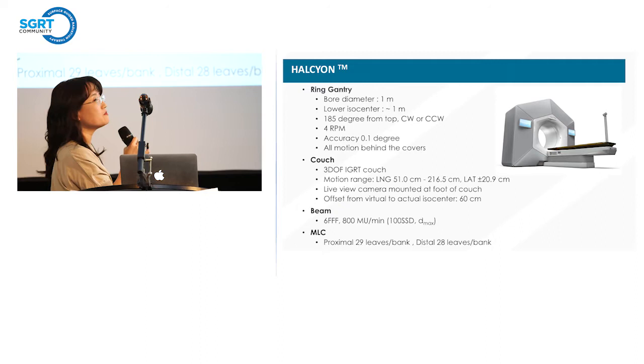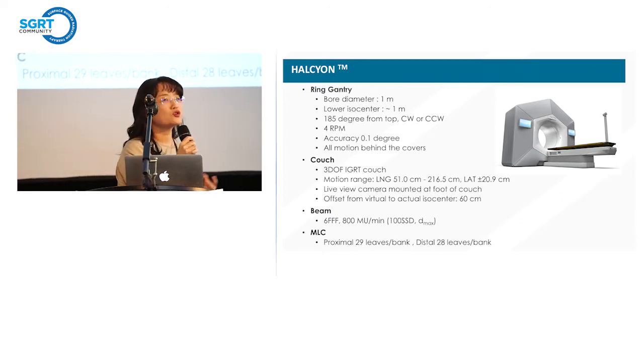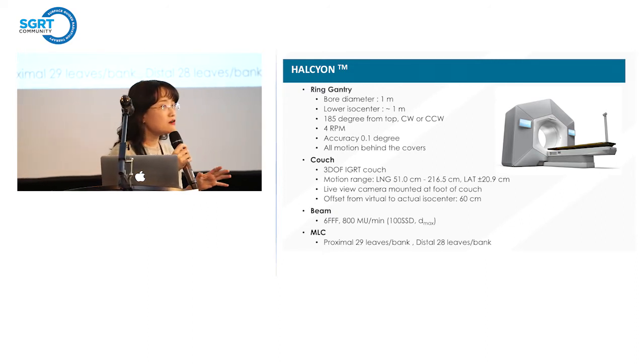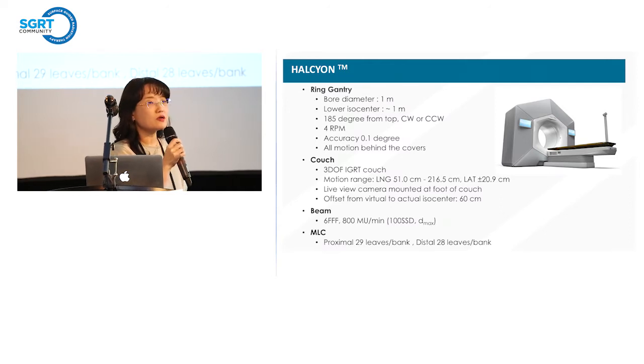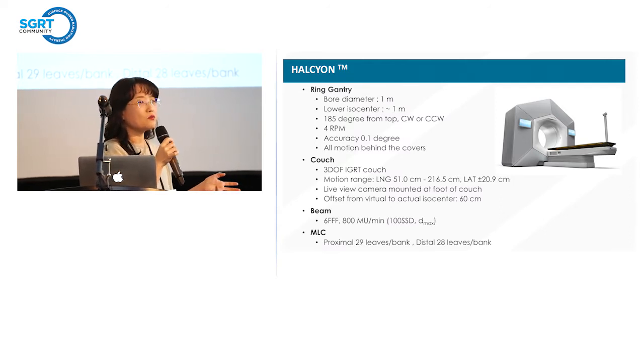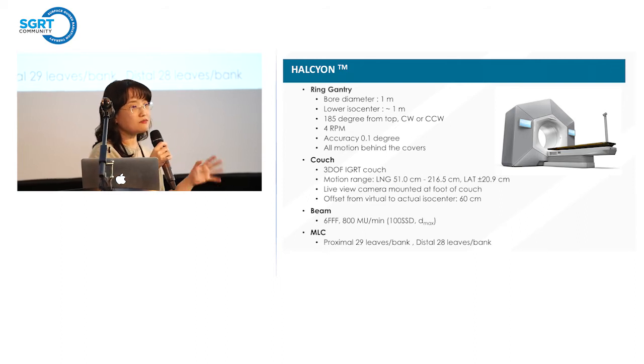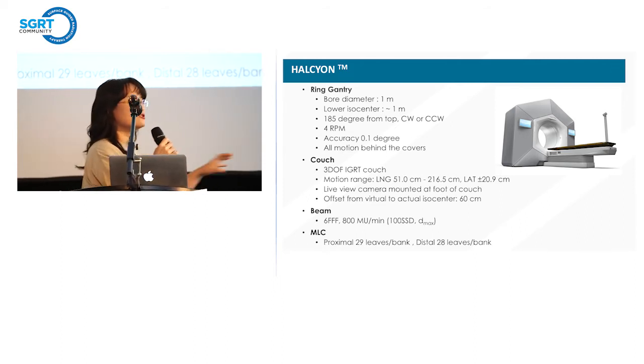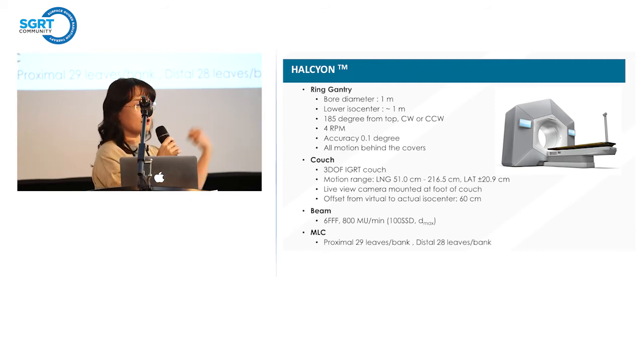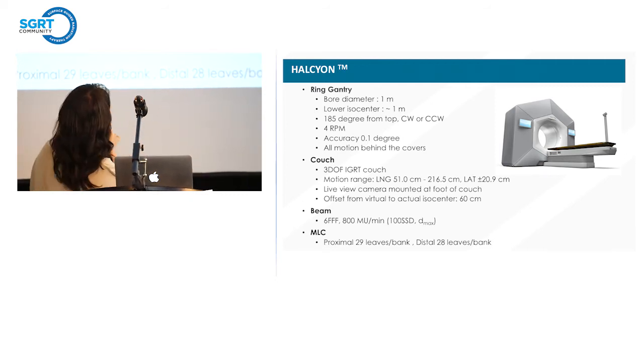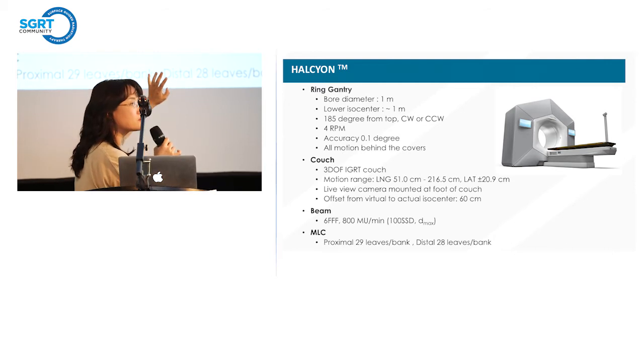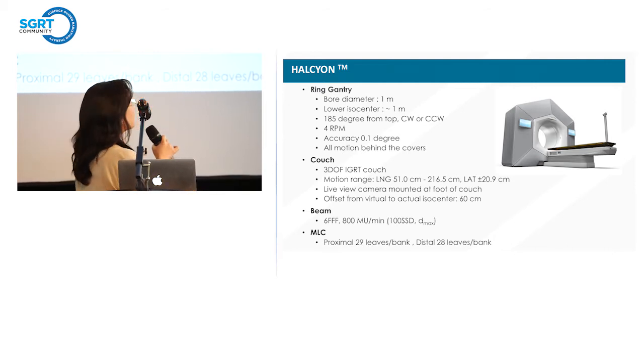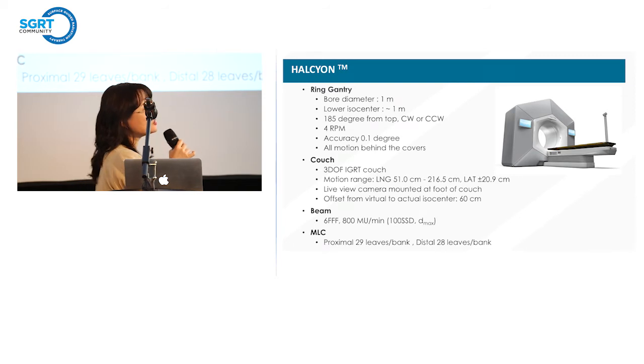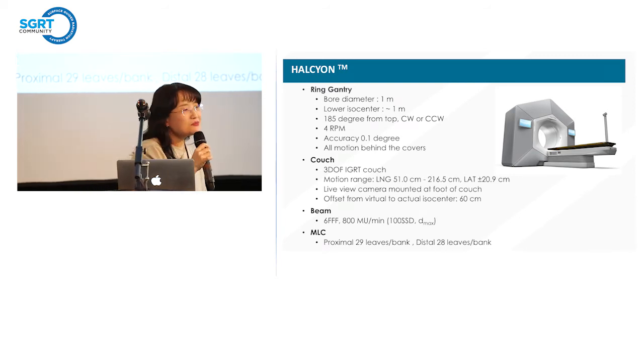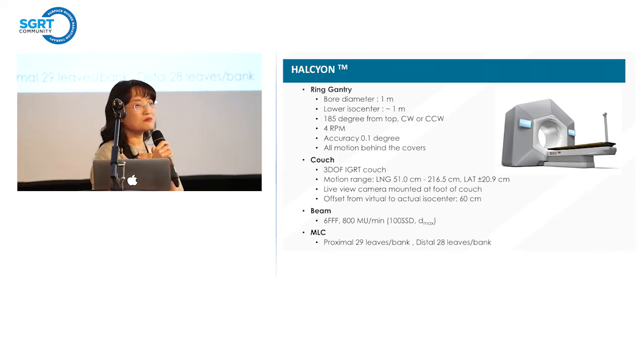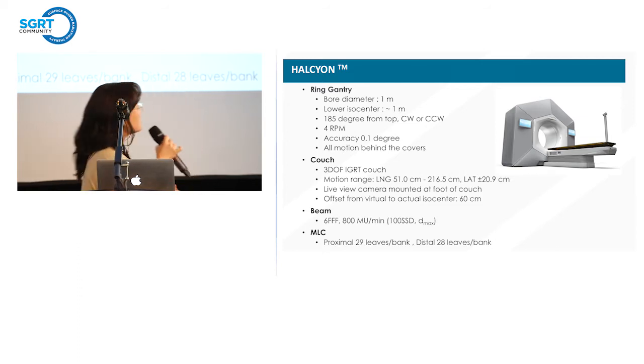So you can imagine how fast the delivery is overall. In terms of delivery time, if TrueBeam is about a 10-minute time slot, the Halcyon will deliver the same kind of beams within 5 to 7 minutes. From getting into the bunker to getting out, it's 7 minutes. All the motion is behind the cover, so there's no worry about collision or any issues. And the couch has 3 degrees of freedom. That's a little bit of a limitation from a physicist's aspect.